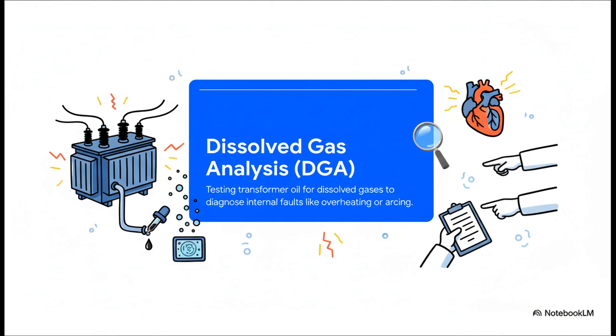This technique is called dissolved gas analysis, or DGA. Here's how it works: when tiny little faults start happening inside a transformer, say a connection is getting too hot or there's a tiny electrical spark, it actually breaks down the special oil inside and creates specific types of gas. These gases are like little warning flags, so by taking just a small sample of the oil and analyzing it, engineers can tell exactly what kind of problem is brewing inside.